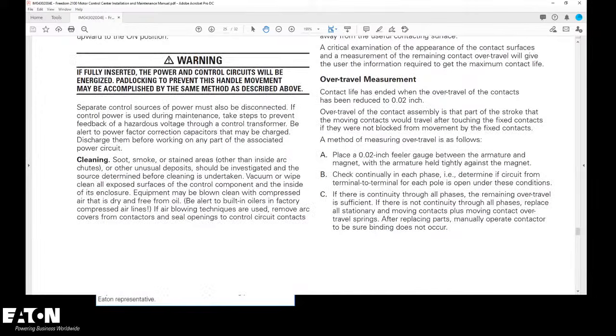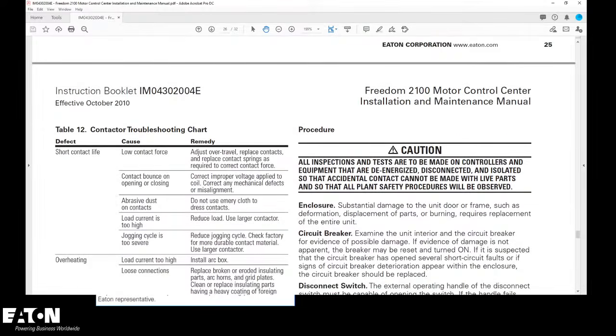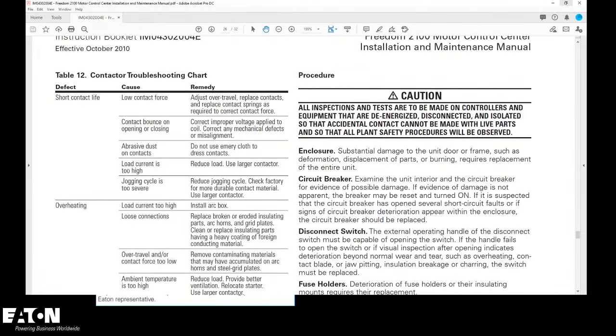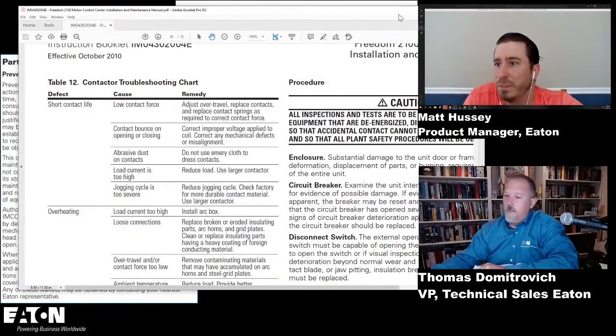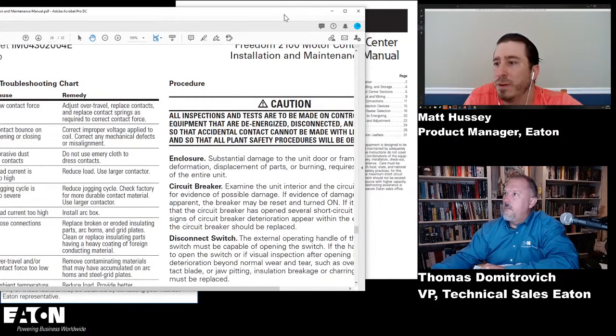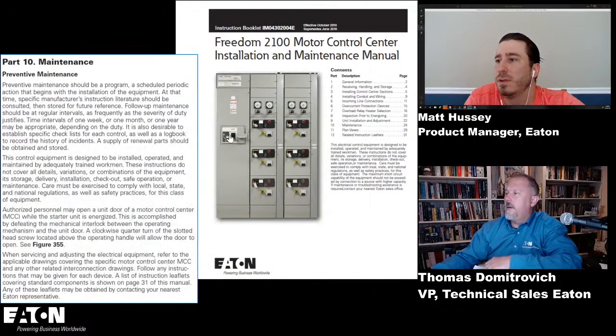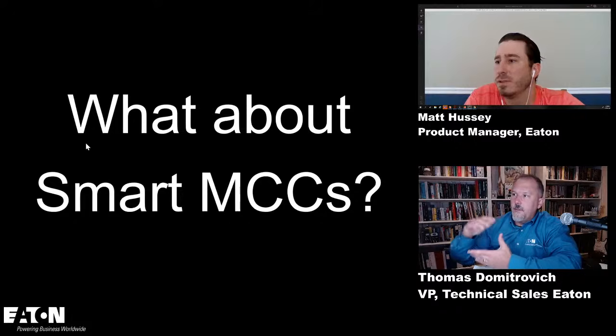You're looking for contact wear. You made that point earlier that the contactors and things like that are always operating. That's typically what you're going to be looking at, right? Right. They're designed for millions of operations, but over time those things are opening and closing on circuits, so you check through those contacts and make sure they're working well. Yep. All right. So I have a reference on that.